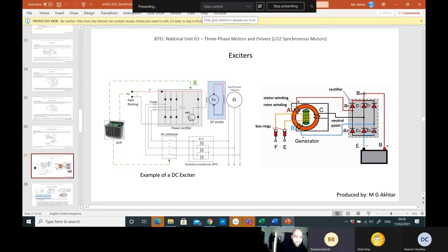Yeah. You've got something called an IGBT. What this in effect does is switch the DC voltage on and off going along here. So you can control the amount of excitation. You can make it overexcite or less excite, because sometimes you've got to keep the excitation level, and you can increase the voltage or decrease the voltage, depending on your needs. As you switch this transistor on and off, you can play with the voltage here. That's the idea behind it.